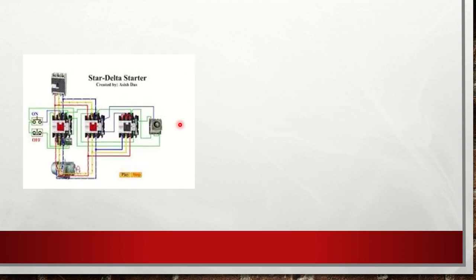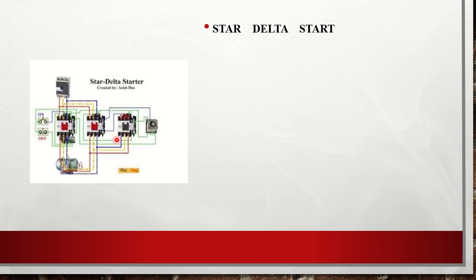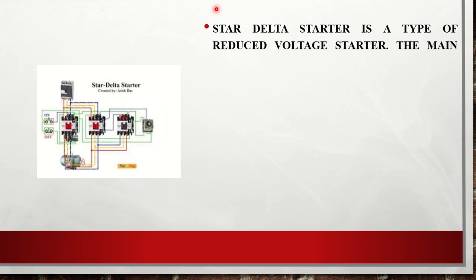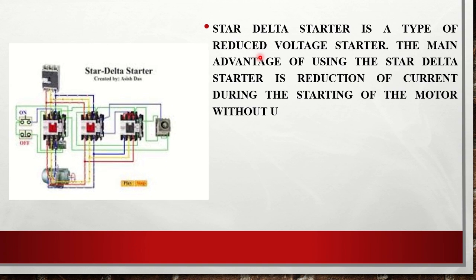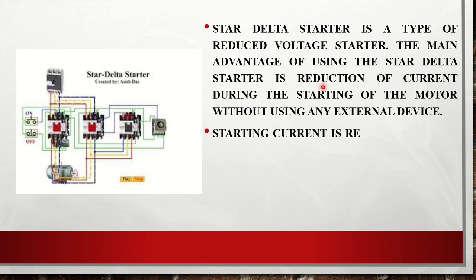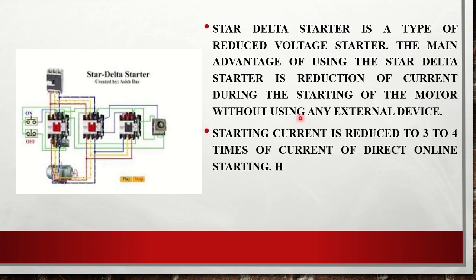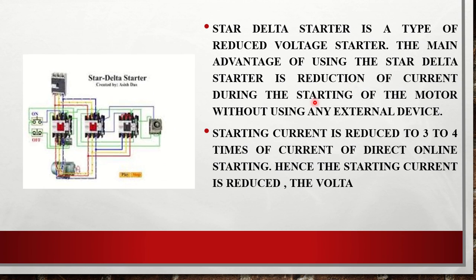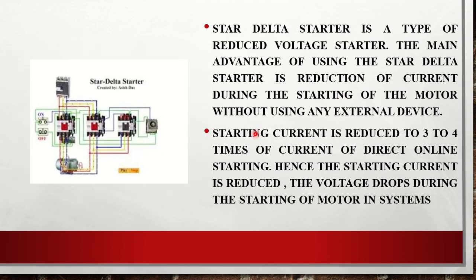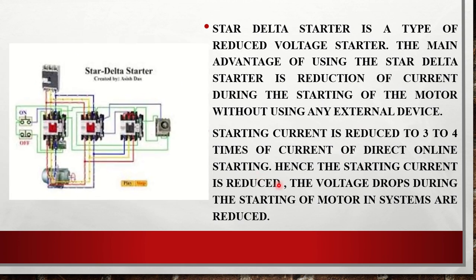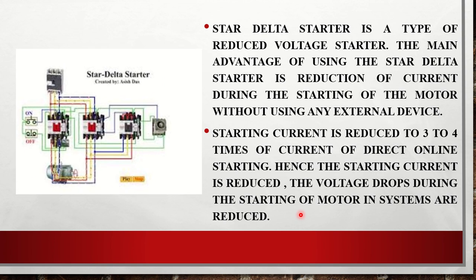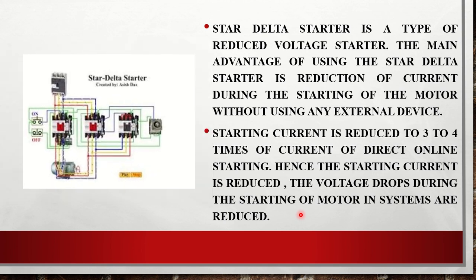The answer is: a star-delta starter is a type of reduced voltage starter. The main advantage of using the star-delta starter is reduction of current during the starting of the motor without using any external device — it reduces the starting current of the motor. Starting current is reduced to 3 to 4 times compared to direct online starting. Hence the starting current is reduced, and the voltage drop during motor starting in the system is also reduced. This is why we use a star-delta starter with any induction motor rather than a DOL starter.